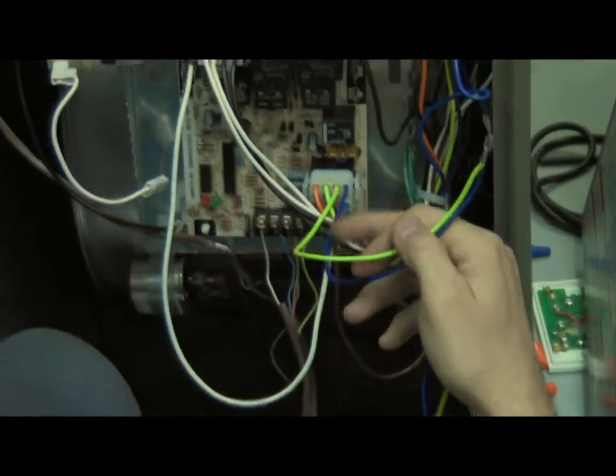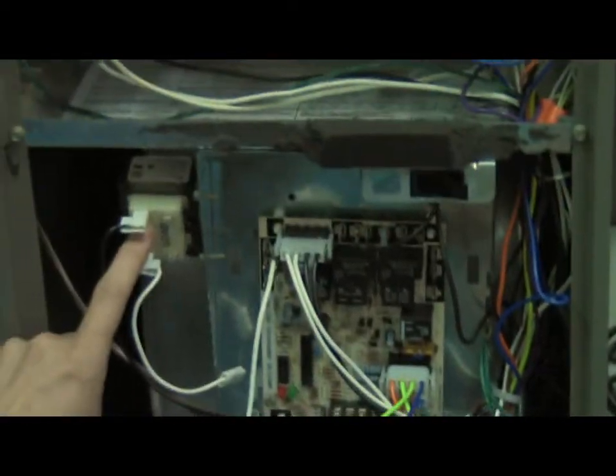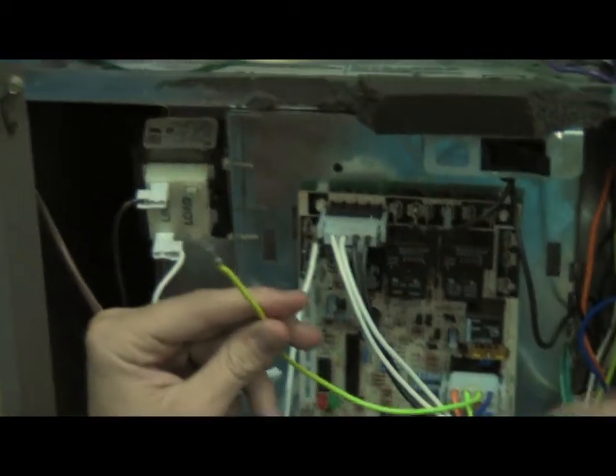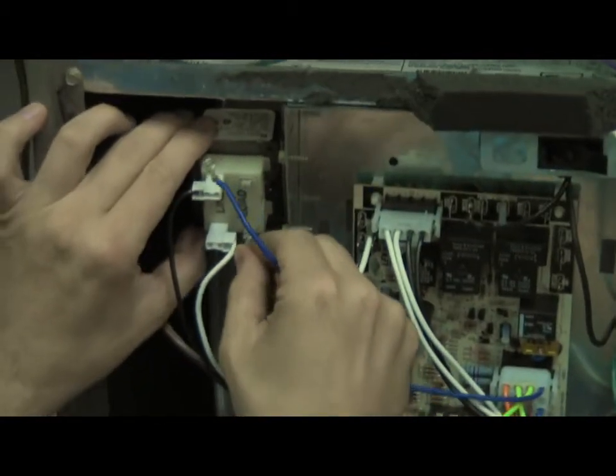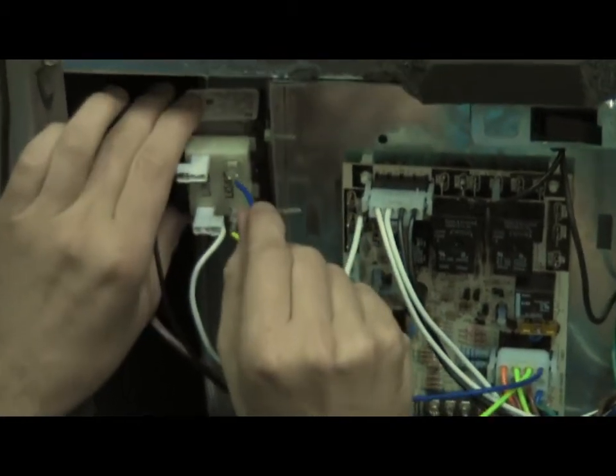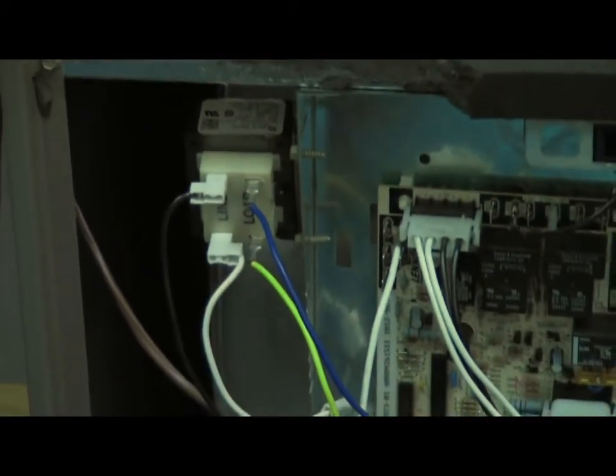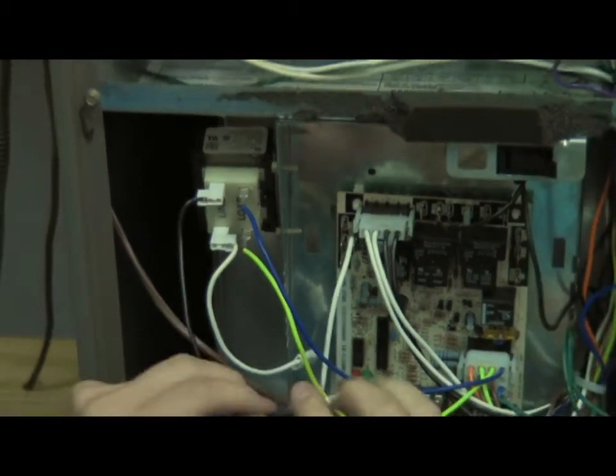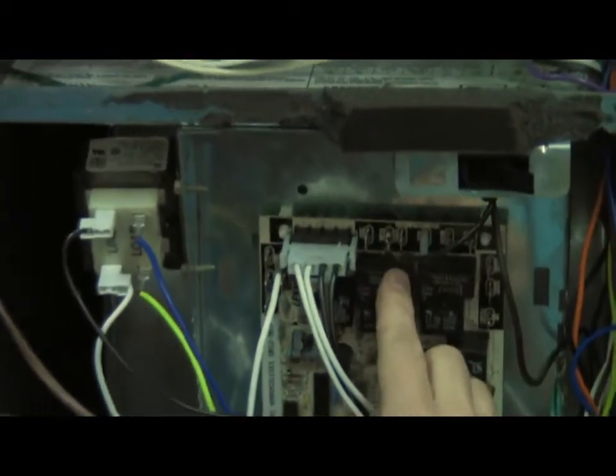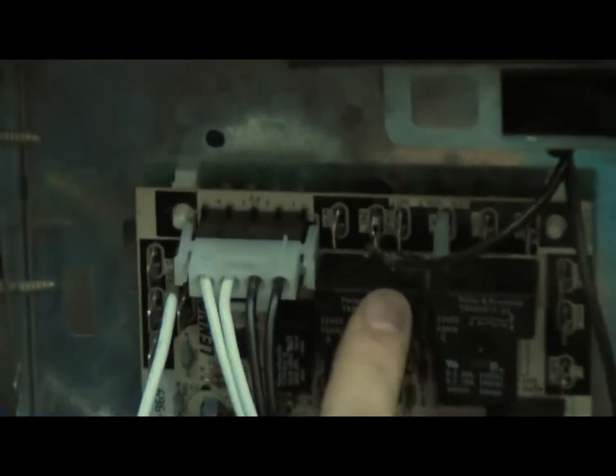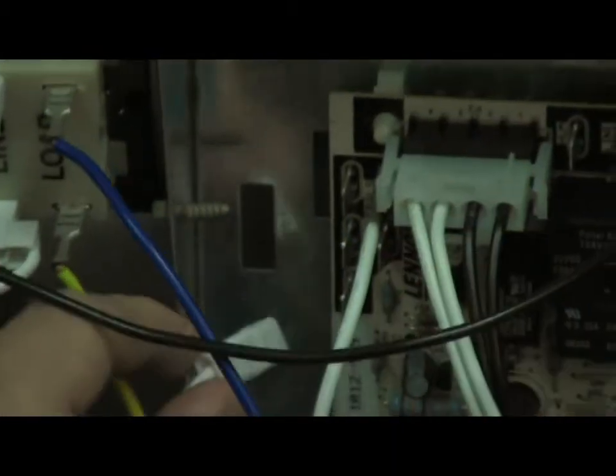Now in order to get 24 volts to the board, you got to attach it to your transformer. This is common 24 volts, and they hook up here on the transformer. Okay, in order for the transformer to get 24 volts to come out of this side, you got to apply 120 volts to the other. Okay, black wire is going to go to a constant 120 volts, which on this control board says XMFR, and then the neutral side of your transformer is going to go to one of the 4 remaining neutral terminals.